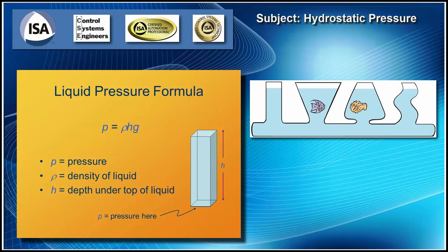Now, a lot of people are confused because they think a really big tank has more force than a little tank. But if you look at these pictures, you'll see no matter what the shape is, they have the same pressure. How do we know they have the same pressure and weight? Water seeks its own level, and you notice they're all the same level. So it doesn't matter what the shape is of the tank. We're just looking at 1 square inch of water extending down in a column and pushing on the bottom, and that is our pound per square inch. So no matter how big the column or how small, we reference it to 1 square inch. Even if the hole is 1/8 inch round, we measure our pressure over 1 square inch reference.